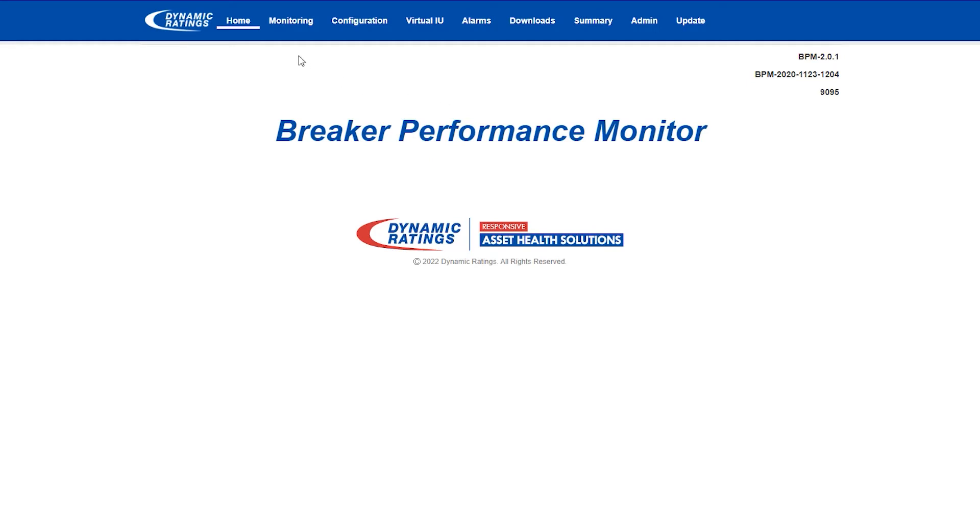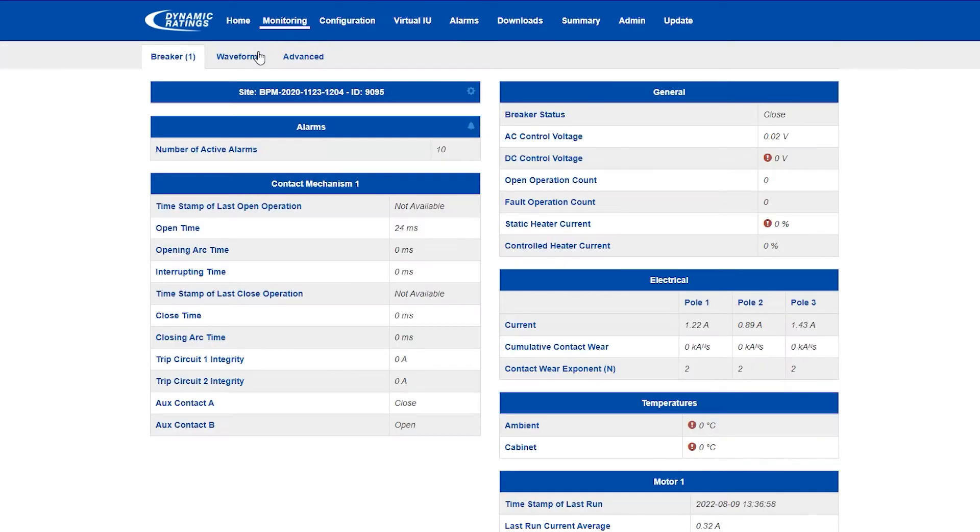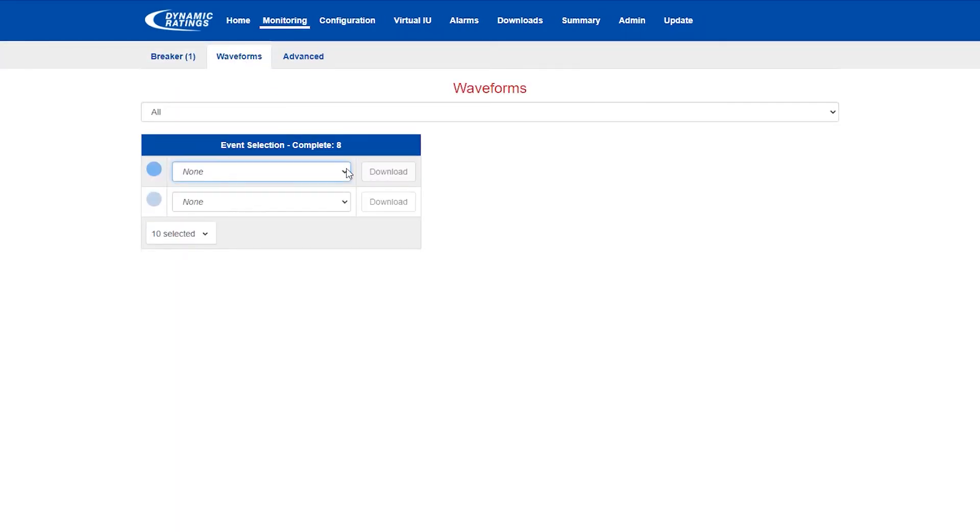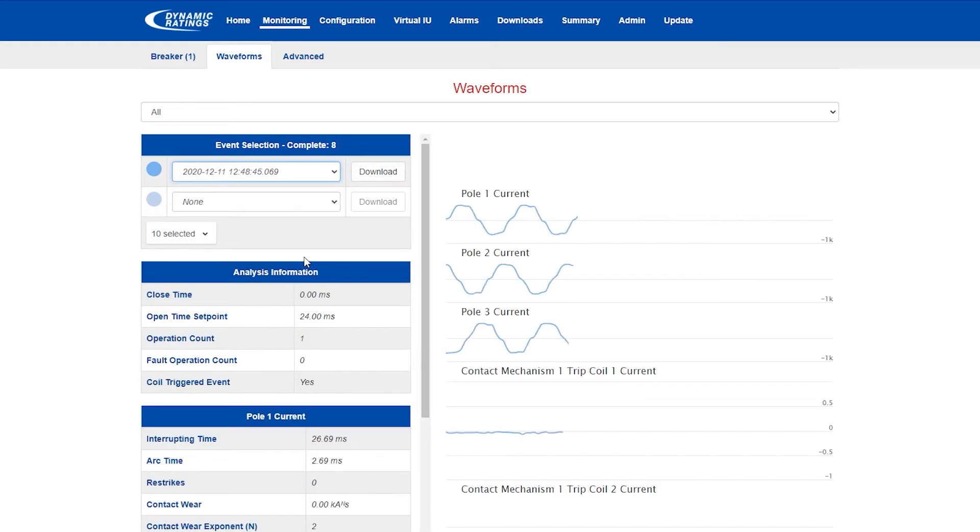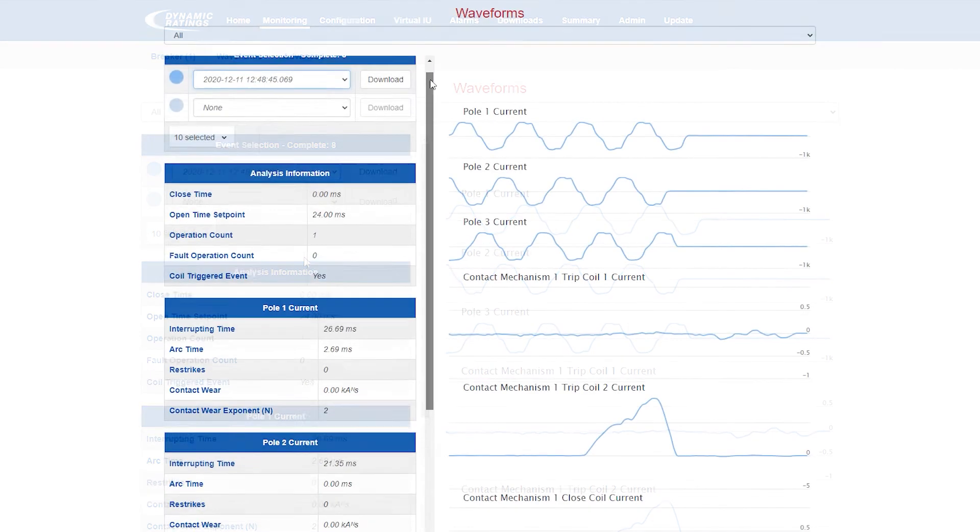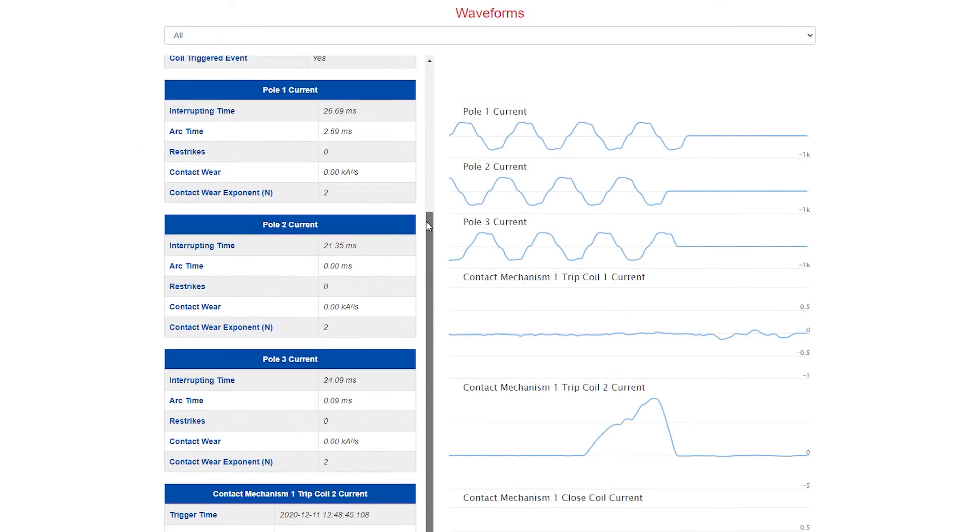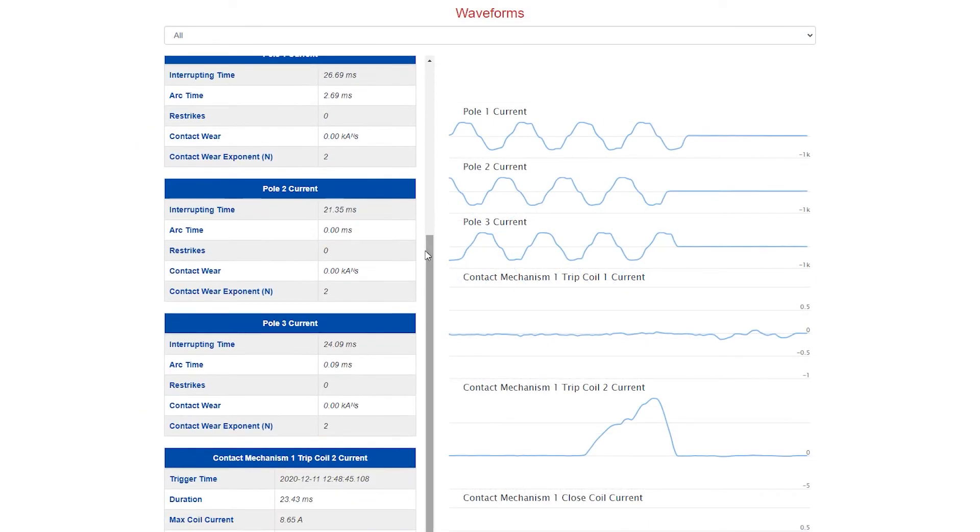Once you are logged in, go to the monitoring tab and select waveforms. From the drop-down menu, select which report you would like to print. Make sure to scroll down so that the coil values and overall interrupting times are shown.